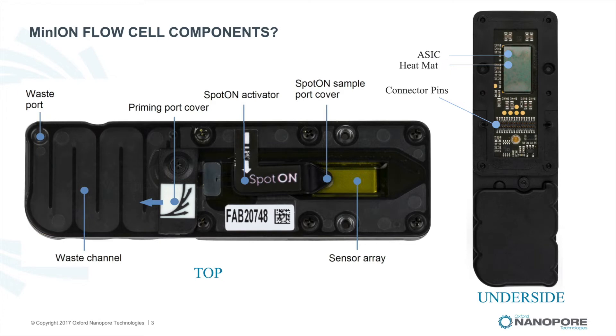On the underside of the flow cell, there are three main features. The ASIC, or application-specific integrated circuit, is connected to the sensor array and measures the ionic current flowing through the nanopores, providing a digital readout of the current flow. The ASIC receives commands from the MinKNOW software to provide control for the sensor array, including acquisition frequency, signal filtering, sensor current range, multiplex input selection, electrode bias potential generation, and deselection of unavailable sensors.